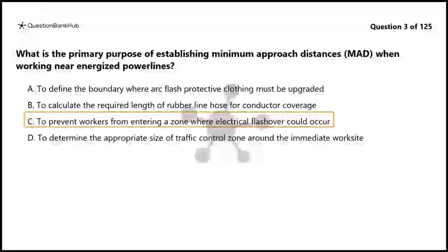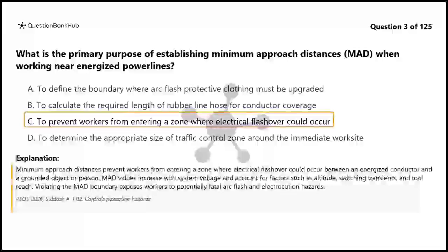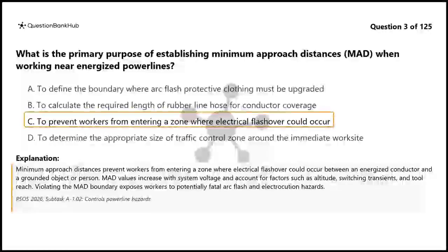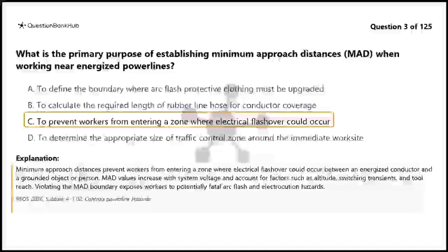The correct answer is C. Minimum approach distances prevent workers from entering a zone where electrical flashover could occur between an energized conductor and a grounded object or person. MAD values increase with system voltage and account for factors such as altitude, switching transients, and tool reach. Violating the MAD boundary exposes workers to potentially fatal arc flash and electrocution hazards.